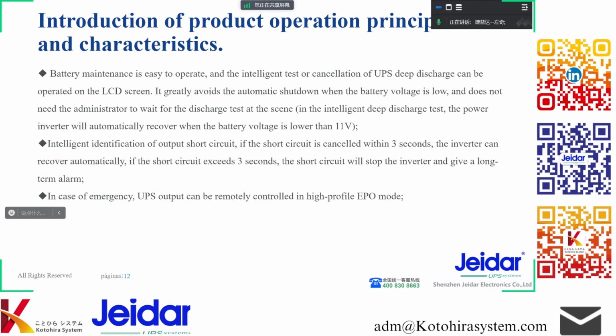Intelligent identification of output short circuit. If the short circuit is cancelled within 3 seconds, the inverter can recover automatically. If the short circuit exceeds 3 seconds, the short circuit will stop the inverter and give a long-term alarm. In case of an emergency, UPS output can be remotely controlled in high-profile EPO mode.